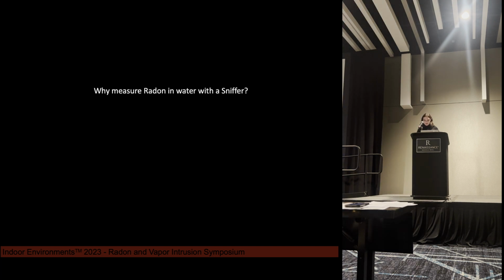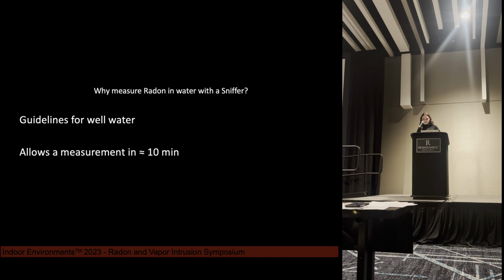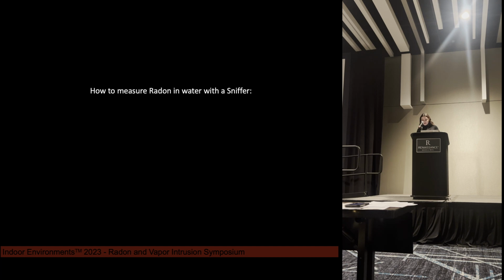So why measure radon in water with a sniffer? Well, there are specific guidelines in place for well water, and using a sniffer allows users to get a measurement within approximately 10 minutes. To measure radon in water, air needs to be continually bubbled through a water sample. This can be done using the exhaust of a sniffer.